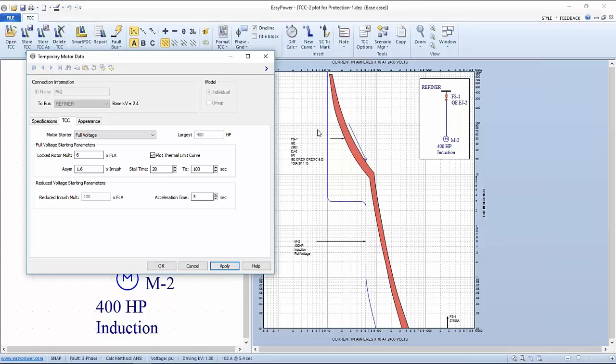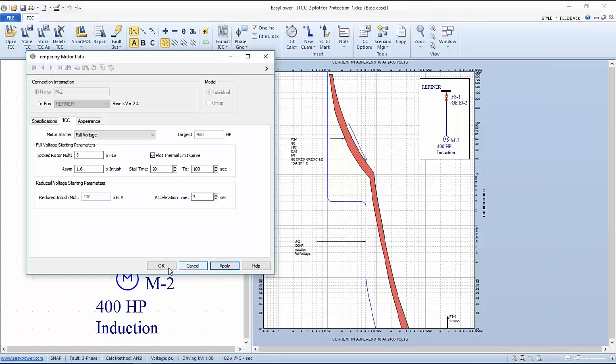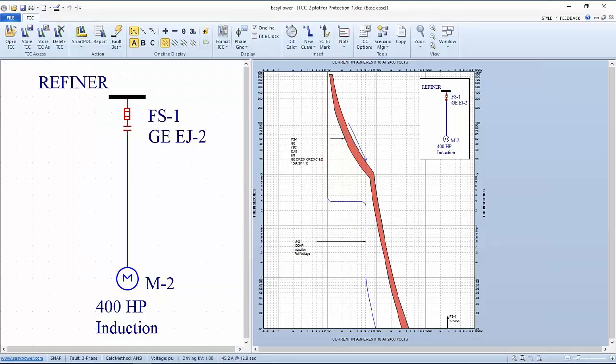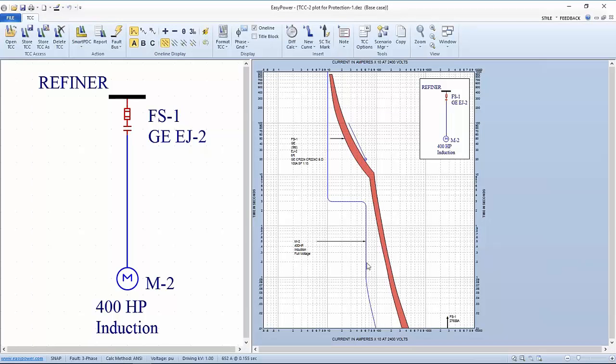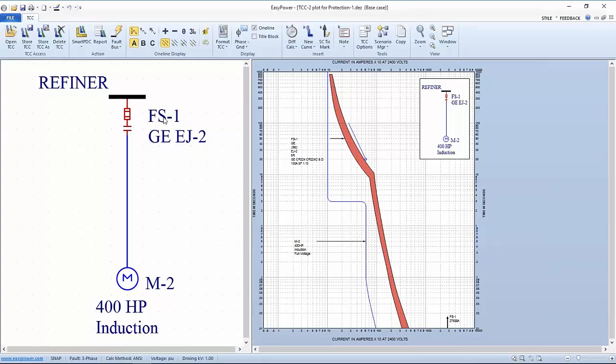The thin blue line is showing me a normal starting current and time for the motor as suggested by the manufacturer. As long as the current doesn't exceed or fall to the right side of this motor starting curve, then we consider that a normal start or normal operation. Consequently, I would not want my fuse to interfere with any current that fell within this envelope to the left. This short stubby curve here that looks like a thermometer tilted to the left, this is the thermal damage curve.